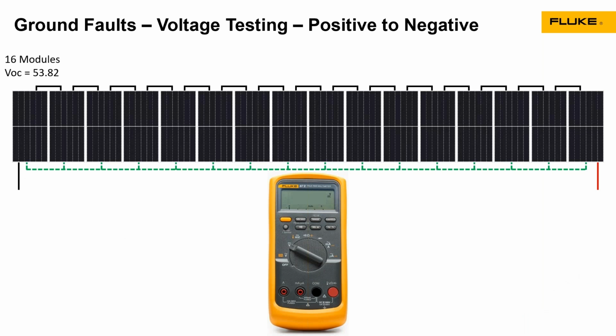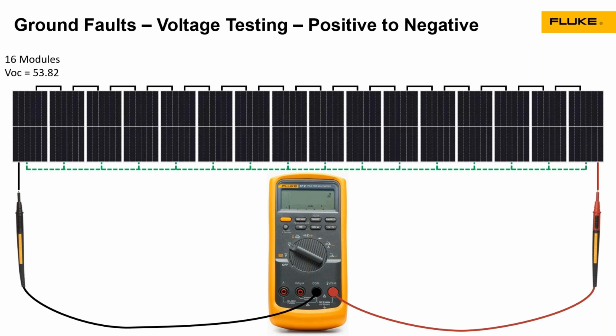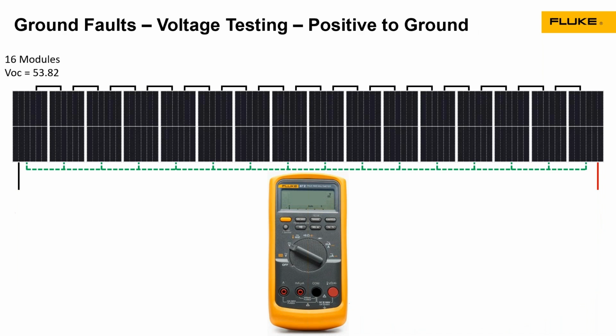So let's take an example of how to use voltage testing to identify the location of a ground fault in a string of solar modules. Here I've got my multimeter. I have a string of modules. This is 16 modules, approximately 53 volts per module. If I test from negative to positive, I should get the open circuit voltage of the string of modules, which is simply the open circuit voltage of an individual module multiplied by the quantity. In this case, I get 861 volts.